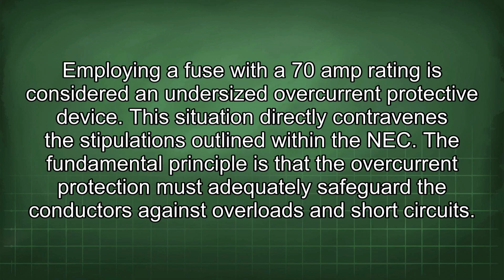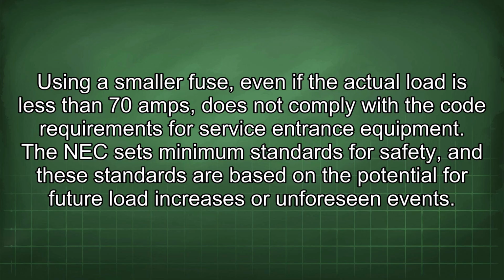Employing a fuse with a 70 amp rating is considered an undersized overcurrent protective device. This situation directly contravenes the stipulations outlined within the NEC. The fundamental principle is that the overcurrent protection must adequately safeguard the conductors against overloads and short circuits. Using a smaller fuse, even if the actual load is less than 70 amps, does not comply with the code requirements for service entrance equipment.